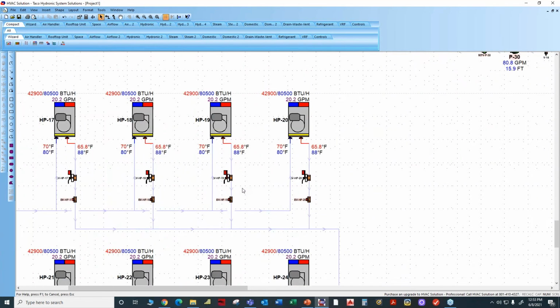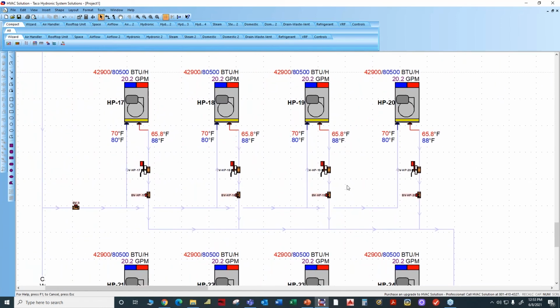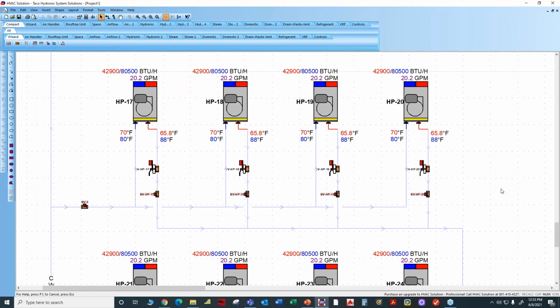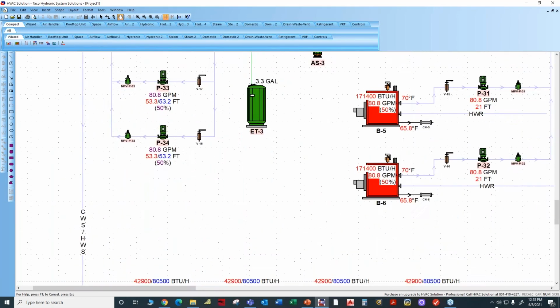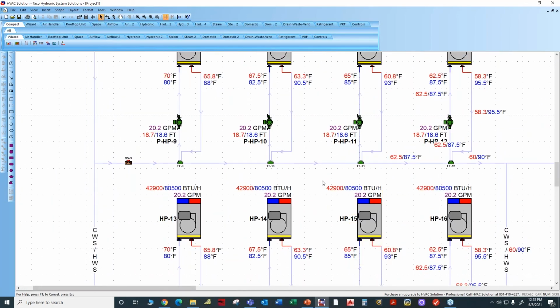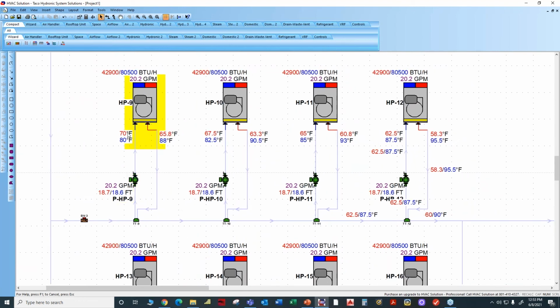So let's zoom back in on the two pipe design. One of the biggest differences in the two pipe design compared to the single pipe design is the entering water temperature to the heat pump. There are other differences, but from an engineering standpoint, that's one of the biggest. If you look at this drawing that Rich has zoomed in on, the entering water temperature for the heat pumps is 70 degrees when it's all heating, and 80 degrees when it's all cooling. It's the same as we are all used to. But if Rich scrolls up to the single pipe, you'll notice the entering water temperature changes as it goes down the line, along that single pipe.